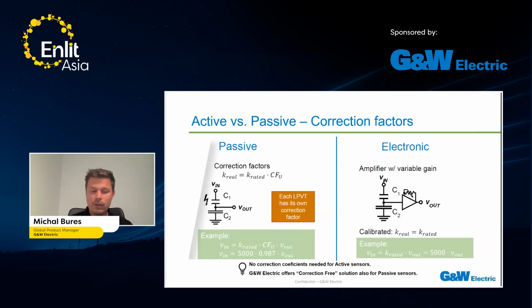So first of all, the difference is in the correction factors. It's very important for the users because in the case of a passive sensor, you need to implement the correction factors into the IED to achieve the accuracy which is guaranteed by the sensor. Each sensor has its own correction factor, so it is important to enter it properly into the IED, because if you switch the sensors, then you will simply not achieve the accuracy.